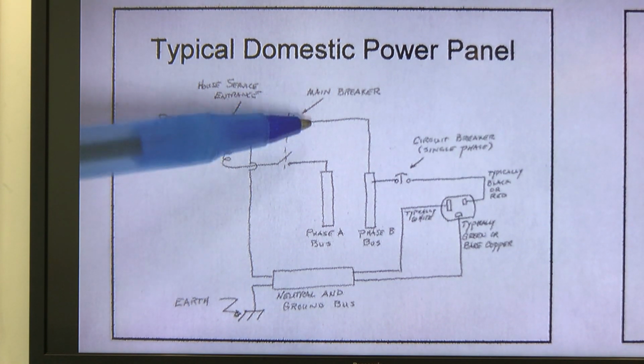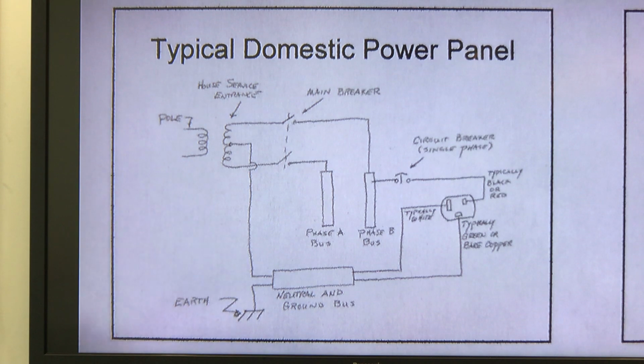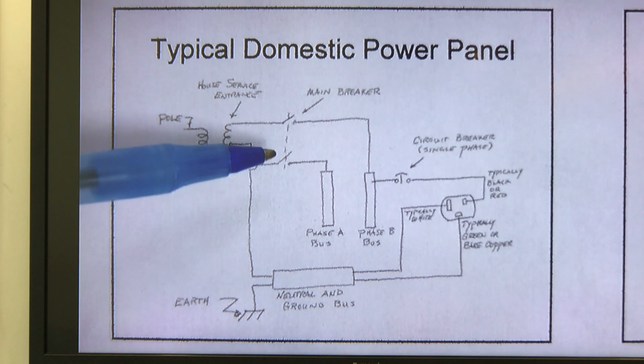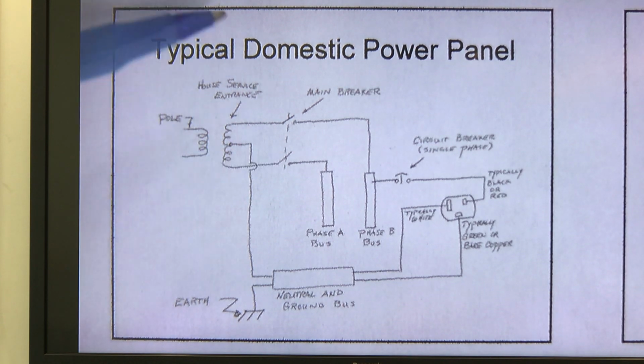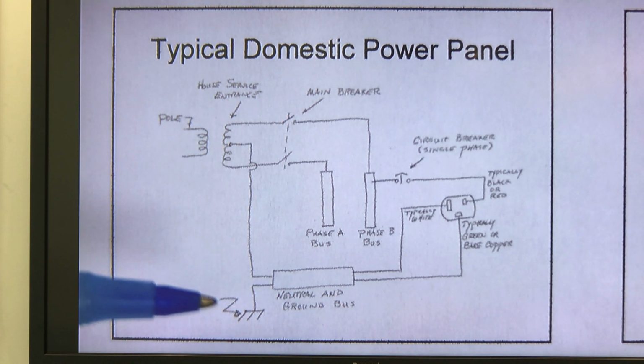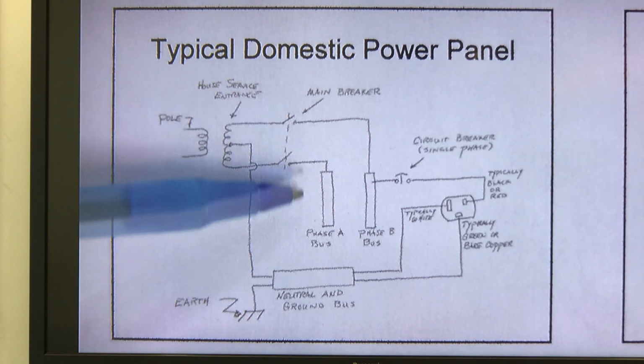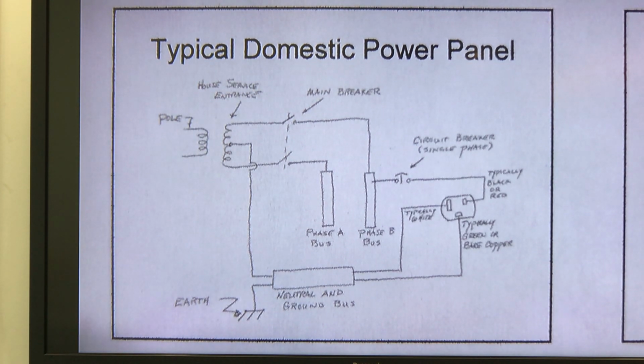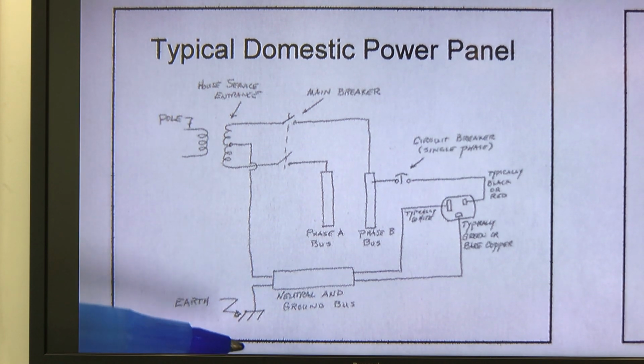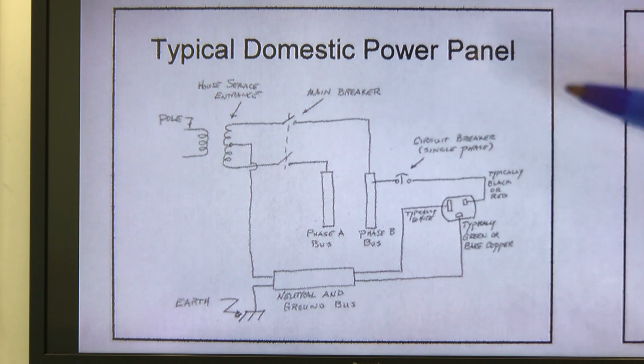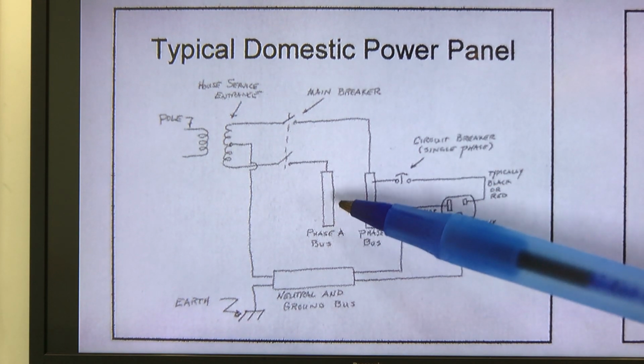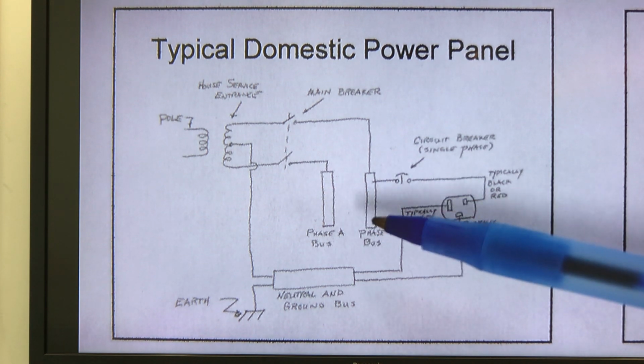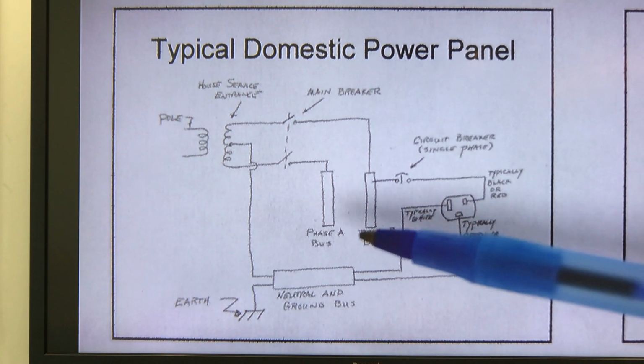Next thing that you encounter, typically at the top of the breaker panel, is a main breaker. And if you'll notice, those are ganged together. So if you trip that out and open them up, then you usually disable both sides of the bus, both phases. So this operates as a single unit, but it controls two different phases. Remember, we have two different phases coming off of the transformer. One side is arbitrarily called your phase A bus. The other side is arbitrarily called your phase B bus, measured with respect to neutral.